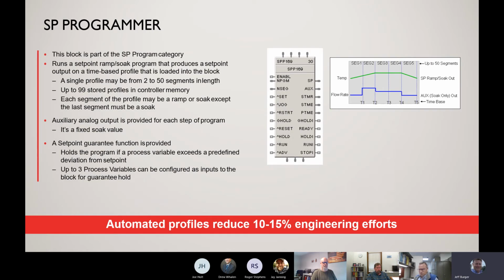Set point program is another function where, in a standard PLC or other control, you would have to use multiple function blocks or multiple configurations to complete the task. But in the Honeywell environment, they offer you one block that's a set point programmer. This is used widely for batch type applications where you need to ramp and soak the temperature or process variable over a specific time. You can have up to 99 profiles stored within the HC900, and up to 50 segments within each one of these set point profiles. There's a whole lot of functionality here that allows you to store all of those profiles under one process controller and one simple function block to accomplish that task.